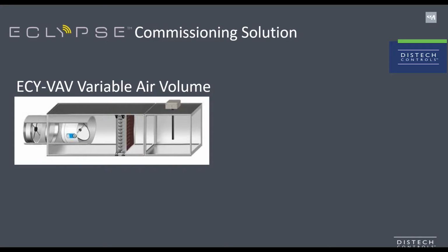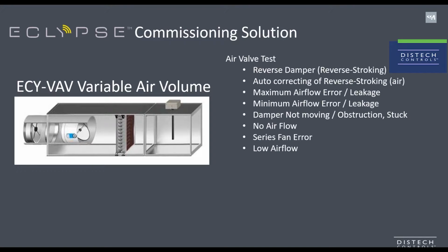Like for the ECY PTU series, your ECLYPSE ECY VAV series controllers are now shipping from the factory with the ability to run a series of functional tests at the edge. One of the most essential tests for a VAV is the airflow test. With the ECLYPSE Commissioning Solution, you will be able to test an entire system and have access to a comprehensive report in a fraction of the time taken to accomplish this task manually.